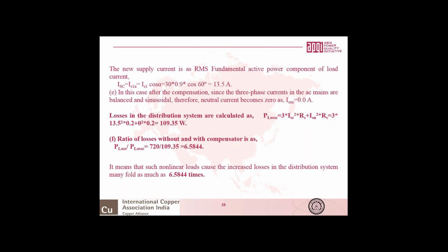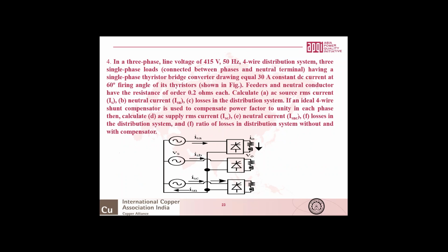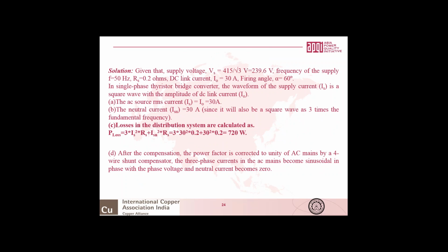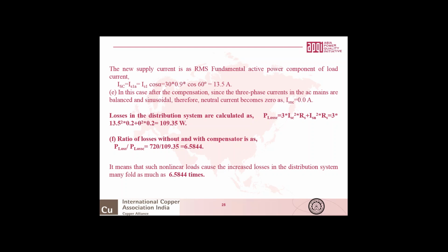So it means that such a nonlinear load causes the losses in the distribution system to increase many-fold, as much as 6.5844 times. This is an interesting example, but it is a simplified one. In practice, with loads like computer loads, the neutral current here is shown equal to the phase current, but in practice the neutral current has often been observed to be around 1.5 times the phase current, and under extreme cases it can go even to root 3 times the phase current, that is 1.73 times. Under such circumstances, you can understand the losses will be many more times than 6.58 times.